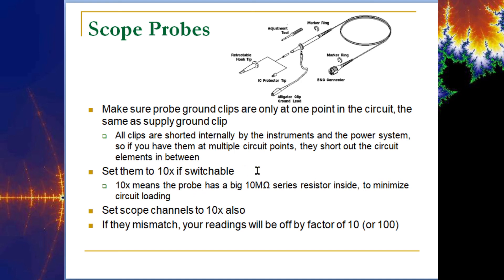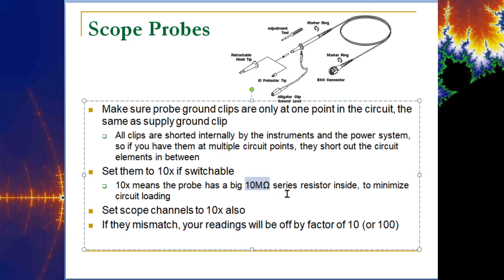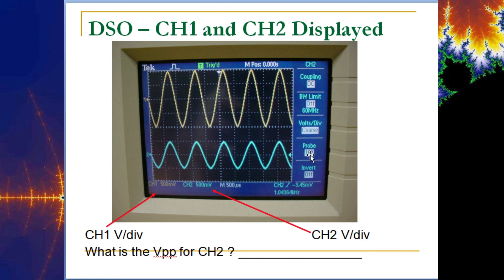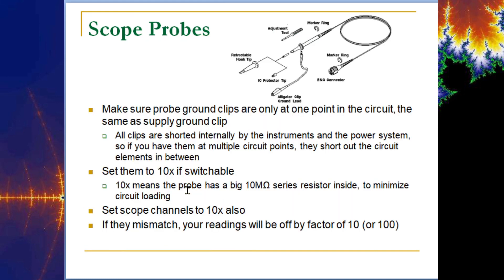Most probes are switchable — they may be a 10x or 100x probe. The 10x setting means the probe has a large 10 MΩ series resistor inside to minimize circuit loading and protect the oscilloscope. This scales the signal down internally. If you have the switch set to 10x, you must set the corresponding channel menu to 10x as well. If the probe switch and the menu setting don't match, your readings will be off by a factor of 10 — a 5V signal might read as 50V.